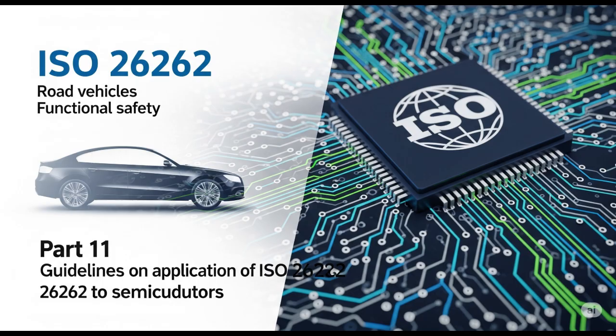A low SPF metric means there are too many potential single points of failure in the design that aren't adequately covered by safety mechanisms. A low LFM metric means there are too many undetected faults, potentially lurking in the background, that could combine with other faults later to create a hazardous situation. These metrics essentially guide engineers to find and eliminate those critical vulnerabilities. Given how rapidly semiconductor technology evolves, estimating those base failure rates must be incredibly challenging, as you mentioned.